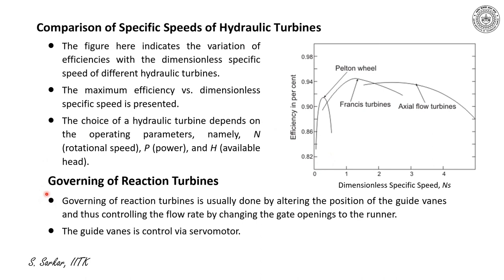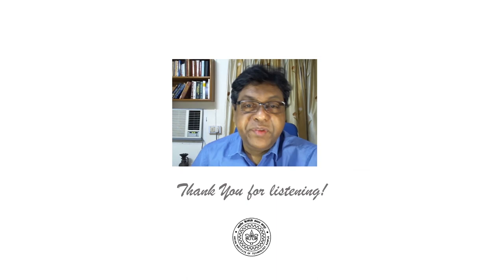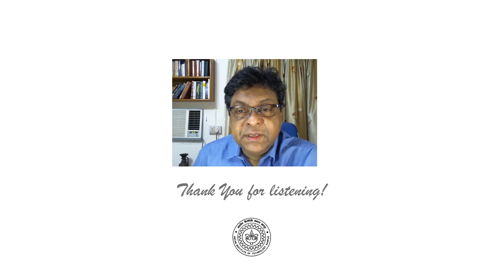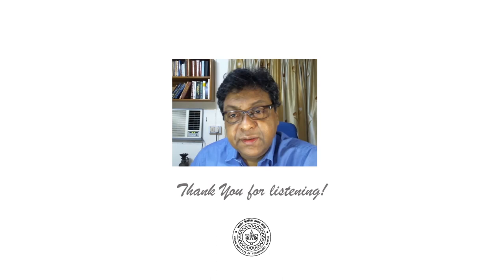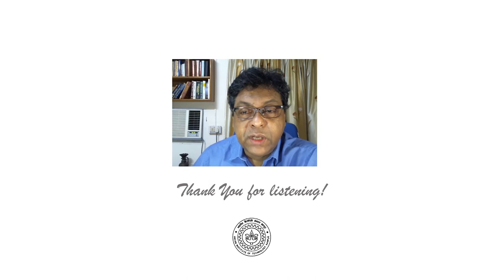Furthermore, regarding the governing of a reaction turbine, it's usually controlled by altering the position of the guide vanes, and the guide vane also is controlled through a servo mechanism as before, or similar to a Francis turbine. Thus, the flow rate is controlled by altering the position of the guide vane at part load. Here I have discussed reaction turbines, both the Francis and Kaplan turbine, about their features, efficiency, apart from constructions.